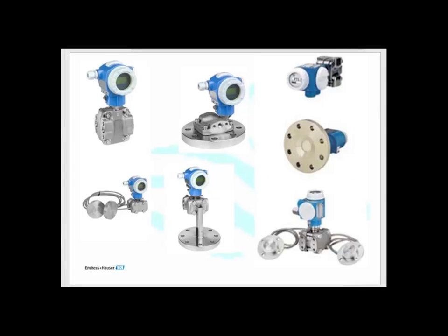Ceramic pressure sensors come in all sorts of mountings. You have the differential pressure type, the flange mounted type - there are several types of flange mounting - and you also have ones such as this one and this one that are set up to measure differences in pressure at different parts of a tank. If you have a closed tank, you need to know the pressure at the top and the bottom, and these two types will give you those two pressures.